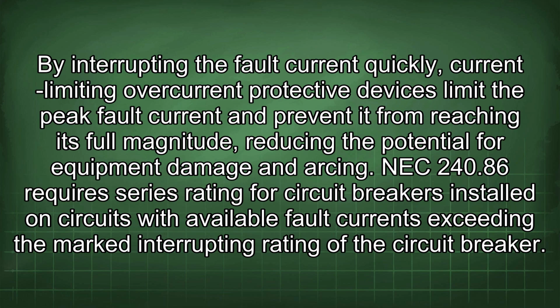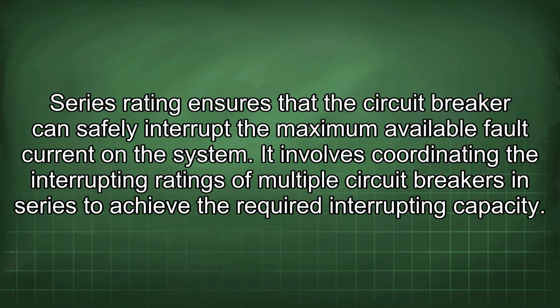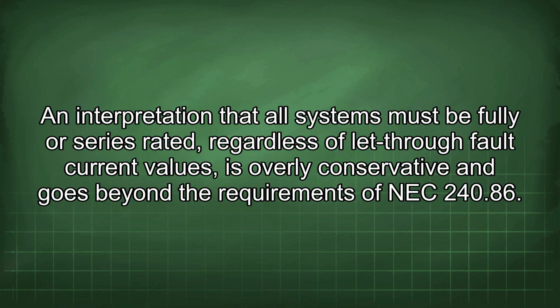NEC 240.86 requires series rating for circuit breakers installed on circuits with available fault currents exceeding the marked interrupting rating of the circuit breaker. Series rating ensures that the circuit breaker can safely interrupt the maximum available fault current on the system. It involves coordinating the interrupting ratings of multiple circuit breakers in series to achieve the required interrupting capacity. An interpretation that all systems must be fully or series rated, regardless of let-through fault current values, is overly conservative and goes beyond the requirements of NEC 240.86.